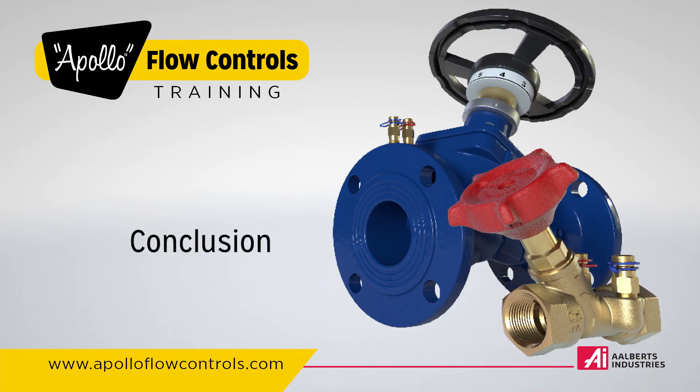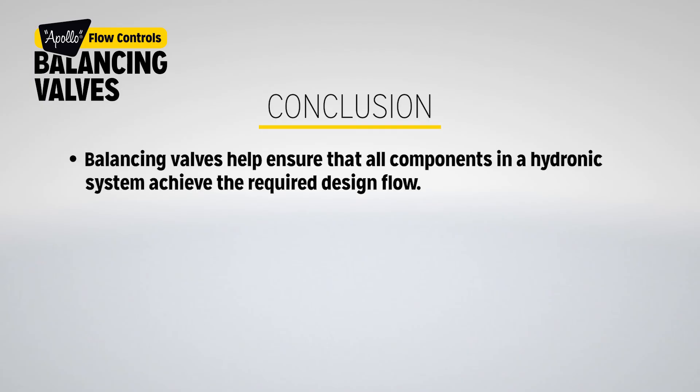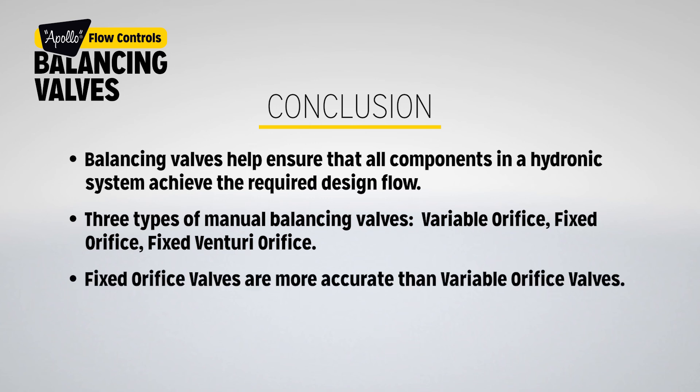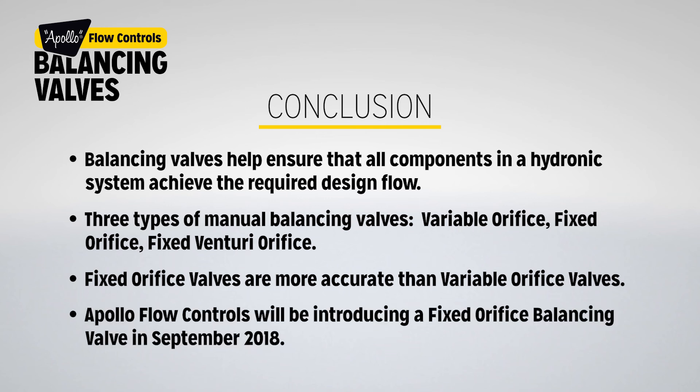Conclusion: balancing valves help ensure that all components in a hydronic system achieve the required design flow. There are three types of manual balancing valves: variable orifice, fixed orifice, and fixed Venturi orifice. Fixed orifice valves are more accurate than variable orifice valves. Apollo Flow Controls will be introducing a fixed orifice balancing valve in September of 2018.